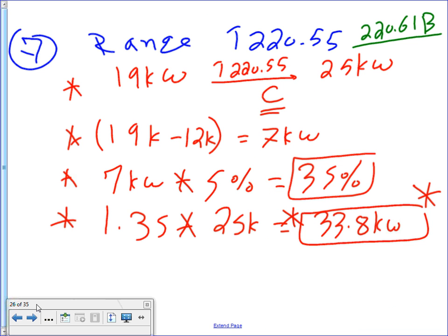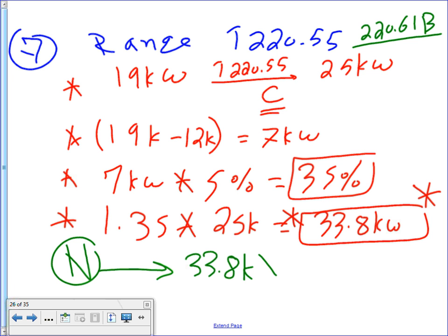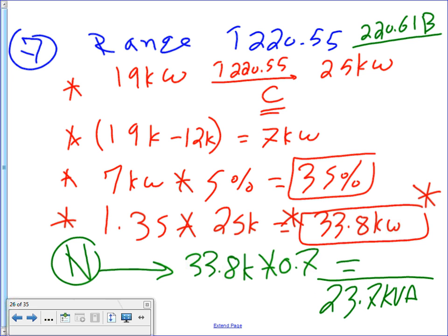For step number 7 for the neutral, I'm going to put my neutral right here. The code says you take the same number, 33.8K, and cut it by 0.7. That's from the NEC code book 220.61(B). And that will get you a healthy 23.7 kVA. Why did I multiply by 0.7, Karen? Because the code says so. Where does it say so? 220.61(B). That's all. Chop it by 70%. Can you see the same calculation, right? The only thing you do at the end, you chop it by 70%.